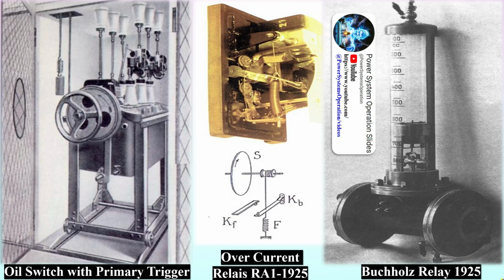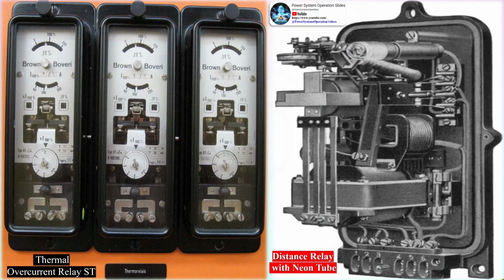Differential relay was developed using pilot wires for conveying information from one end to the other end of the line. In 1923, distance relay appeared in the form of impedance. Later, the induction-type mho relays with very high precision came into practice. After that, polarized DC relays with better accuracy and sensitivity were developed in 1939. All of the relays developed until the 1940s were electromechanical relays. These devices achieved very high precision and sensitivity in the form of induction cup mho relays and perform well for the missions attributed to them.